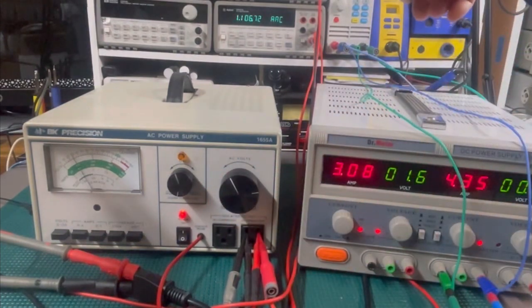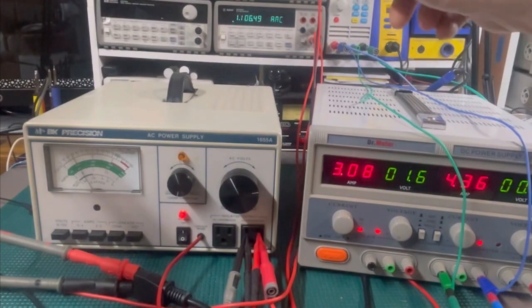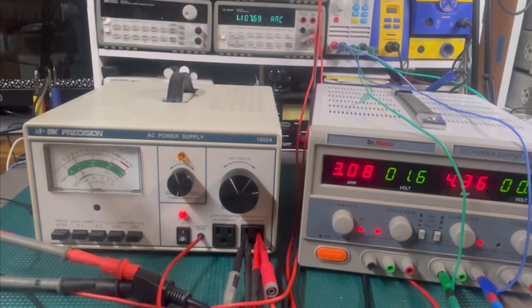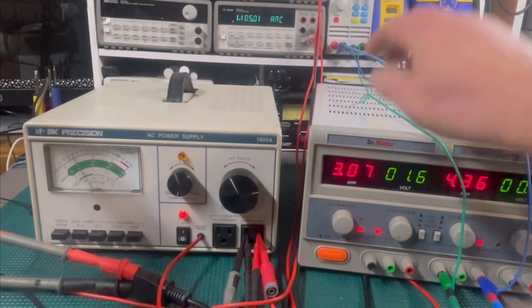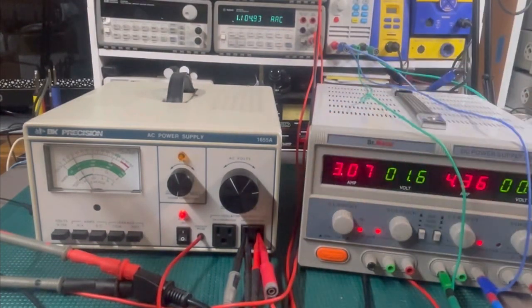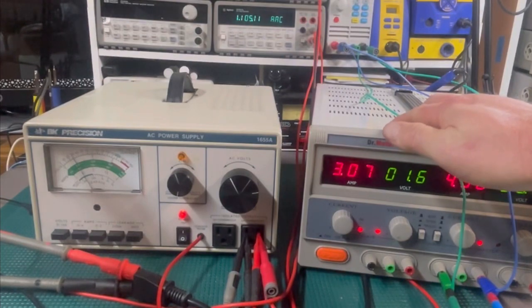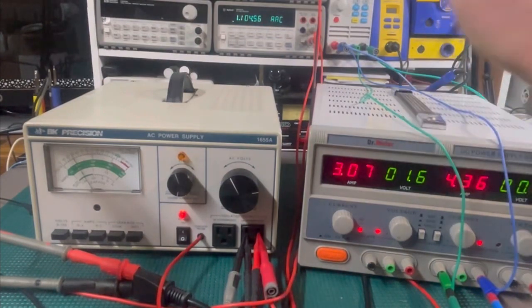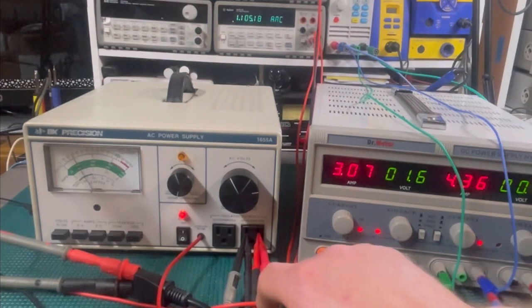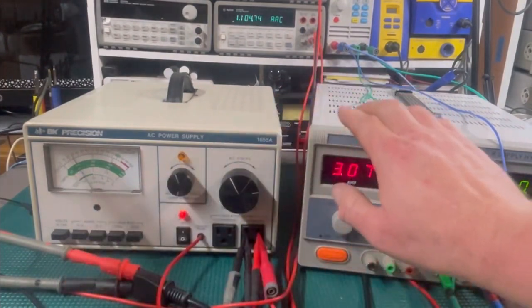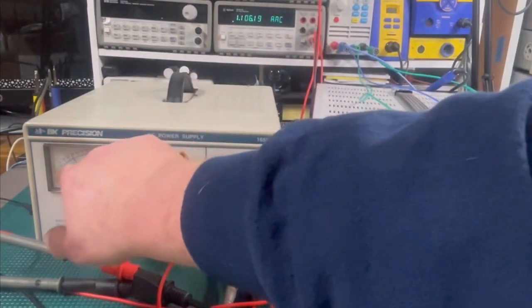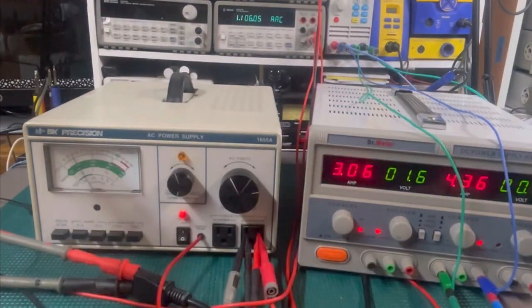Now, as you see, I've already got it set on this end. I've got it set to only about 7 amps. You know, that gauge isn't accurate really on that load per se, but I've got it set to about 7 amps draw here. And this has hit the constant current already. Oh yeah, it's because I've got the current turned down. I turned the current down on this so this would draw less through this, so that we're only reading 1 amp exactly on the scale here.